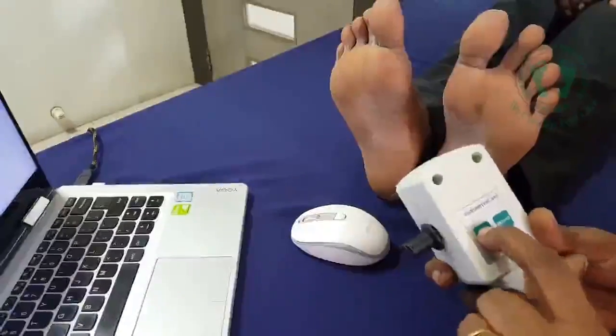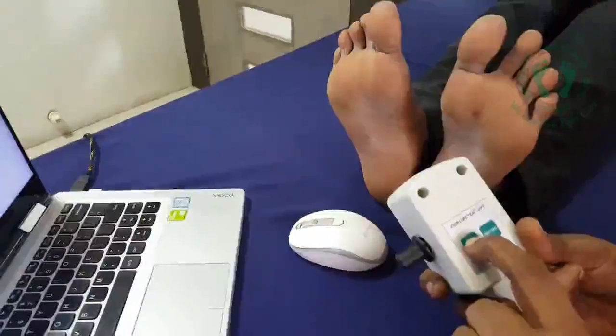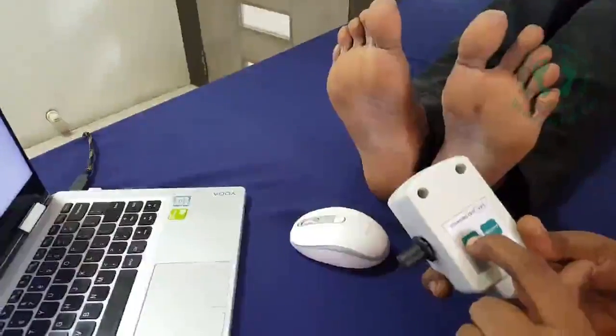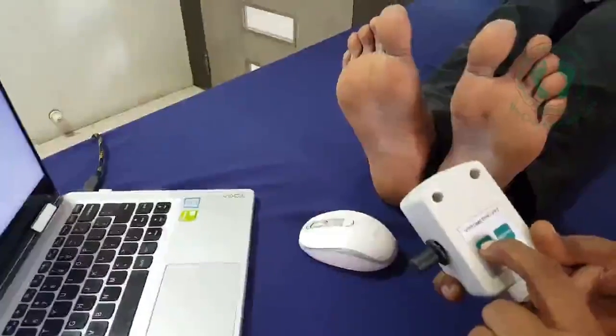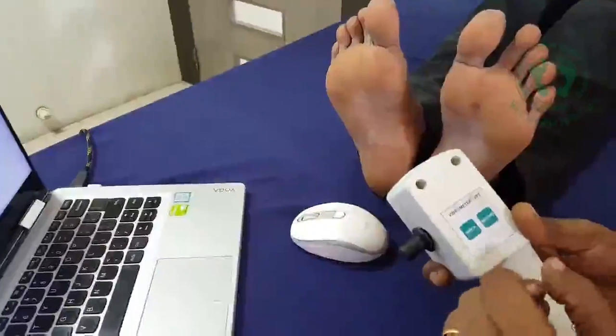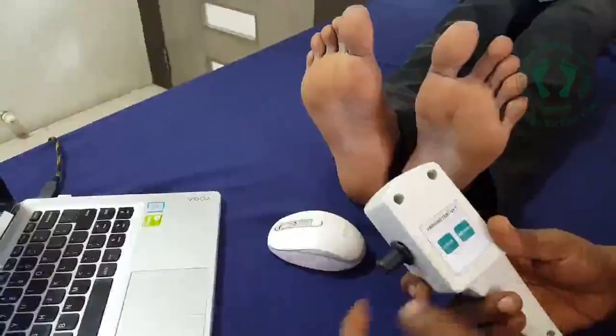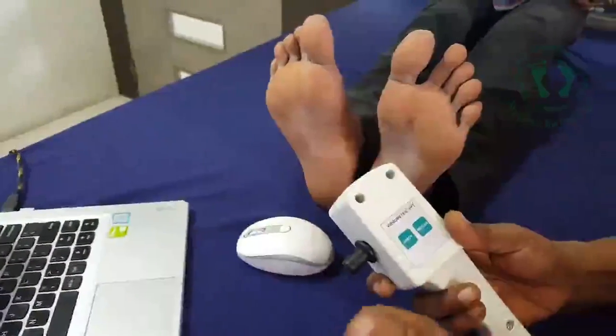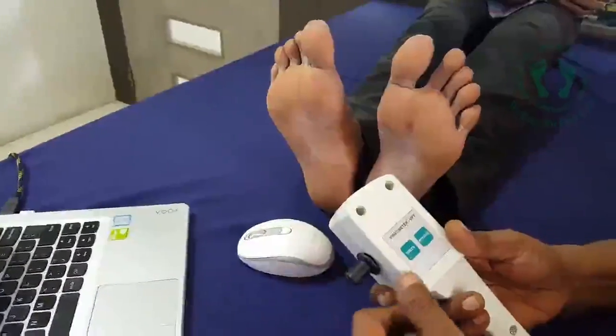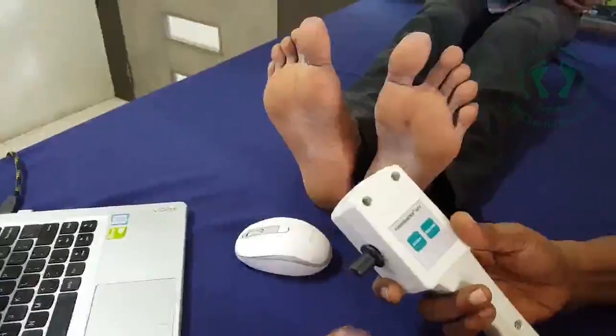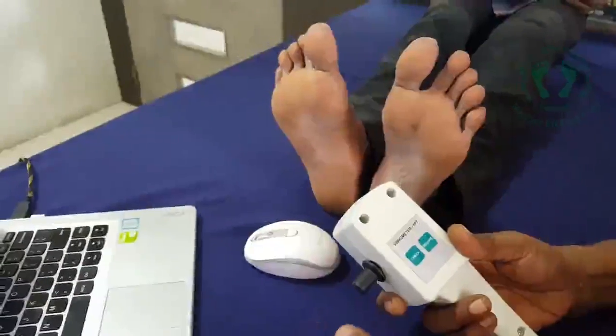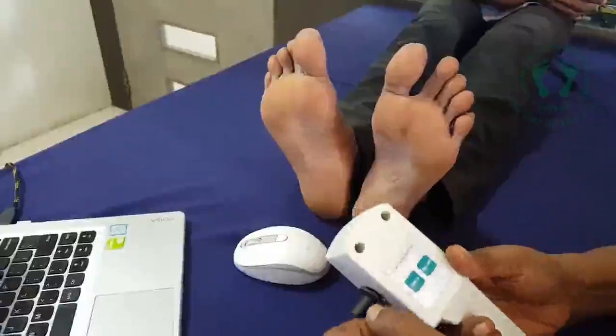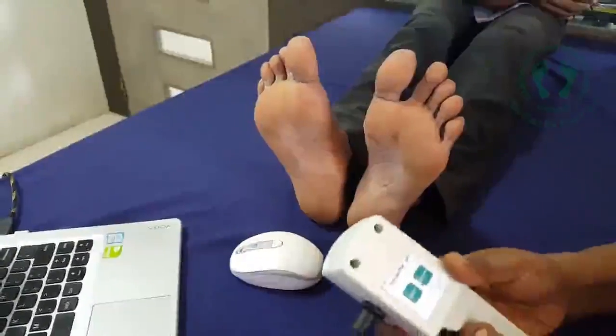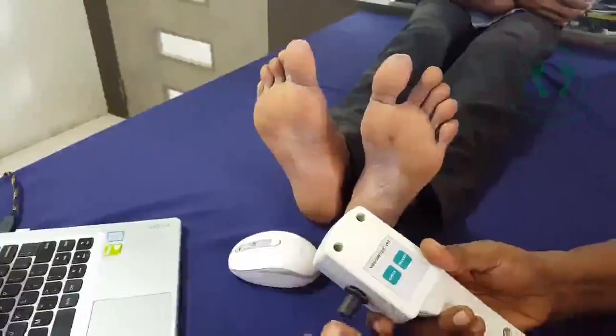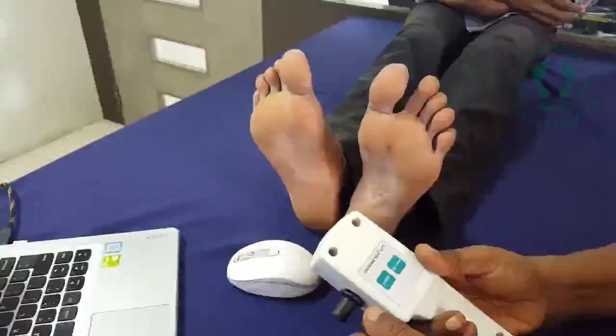Even if I am stopping it, if the patient says I am feeling it, then probably it's the touch, not the vibration. Then we have to increase the voltage and see whether they are getting it. Suppose even at 50 volt they are not getting it, that means they lost the vibration perception. Or we can again go back to the hand and show them the touch and the vibration and make them aware, and then we can restart the test.